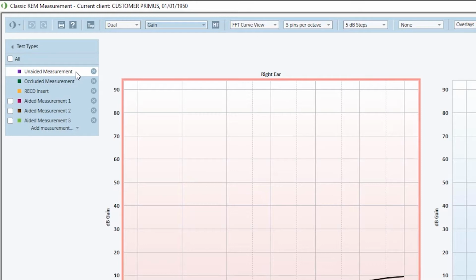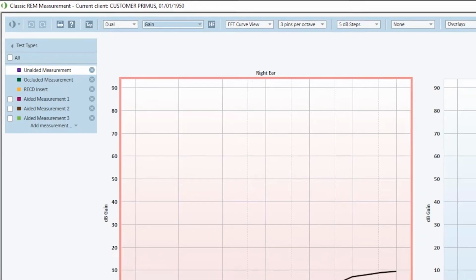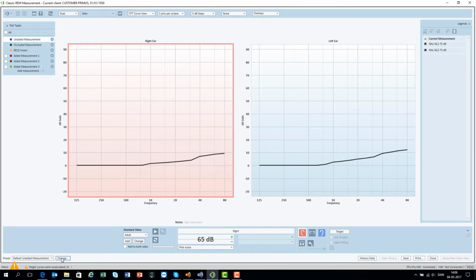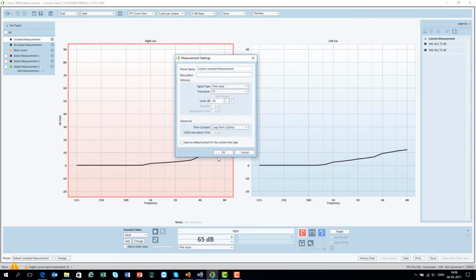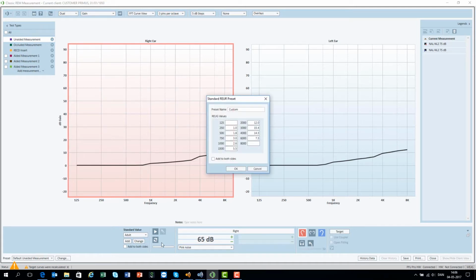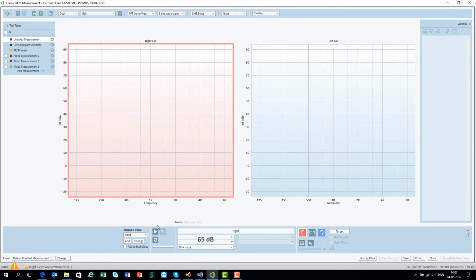For children, real ear to coupler difference. Primus provides predefined editable settings such as how to change signal type and measurement start level. If anything is changed, remember to save. To operate the REM measurement, use the Primus control panel below the graphs. An average real ear unaided gain value can be added and used if the measurement cannot be performed correctly. To start a measurement, click on the play button or use the space bar.